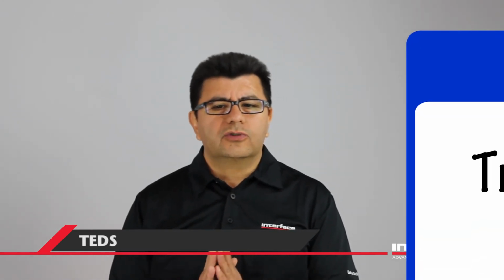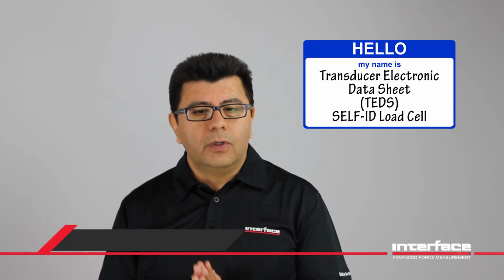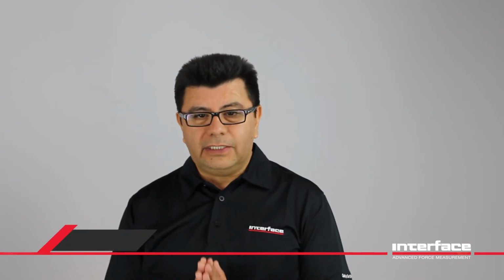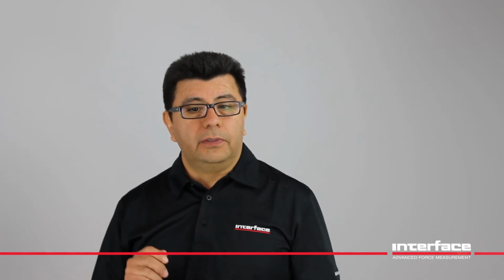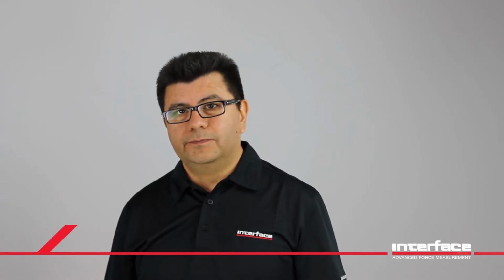TEDS. TEDS stands for Transducer Electronic Data Sheet, and is most basically a load cell with electronic identification inside, including sensor information and calibration data. It meets the standard IEEE 1451.4 for smart transducer interface. It will make a load cell plug-and-play ready, can reduce instrument setup time, and eliminate data entry errors.